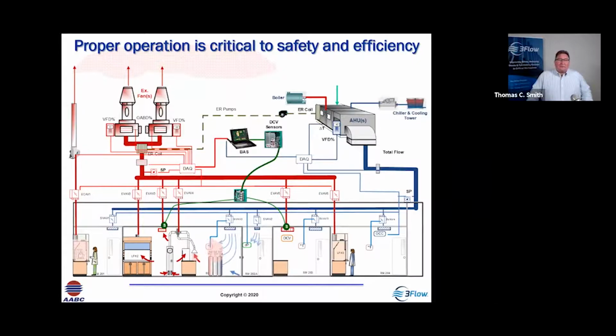So let's get some airflow through the building. And as we expect a system to modulate flow, as they open and close the sashes or the labs are going occupied or unoccupied, then we expect that the flow is going to modulate from the hoods and translate all the way up to the exhaust systems. Now, if this airflow is modulating through the exhaust system, we have to also anticipate that the air supply is going to modulate in tandem, and so that they're going to be working in a lead-lag type of arrangement. But in order for us to ensure proper air balance for the building, there can't be a wide variation between the exhaust and supply. We want them to match, and they need to modulate in tandem in order to achieve that proper balance over the whole range of operation.